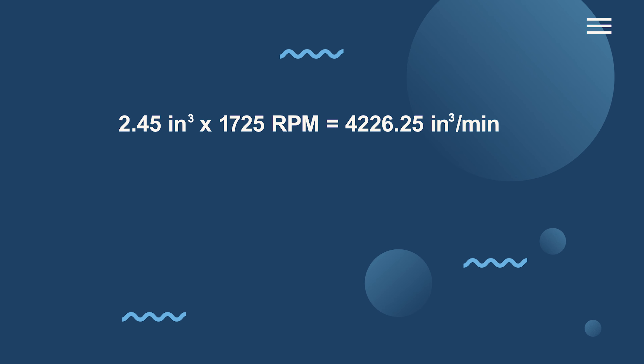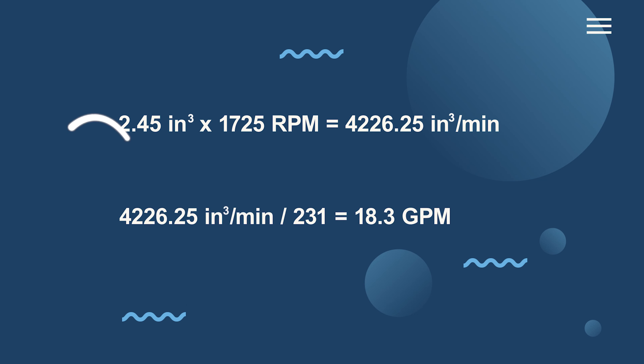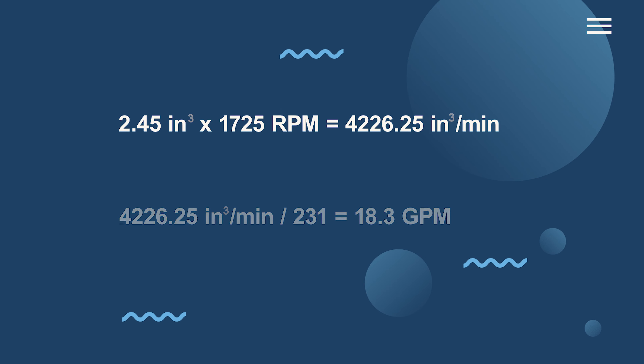This can be converted to gallons per minute by simply dividing the cubic inches per minute by 231, leaving us with 18.3 GPM. Now that you understand how to calculate pump flow, let's talk about efficiency.